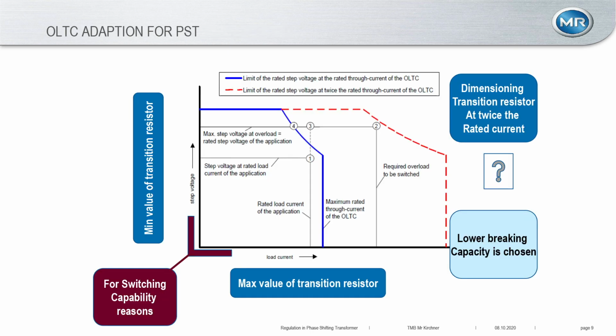If you look at point 1, that might be our working point for the onload tap changer. So that would be with nominal current. And now you would think everything is fine. And usually the standard would tell you that the switching capacity of your onload tap changer must fulfill the need that you can increase the load current to twice the nominal current, and then you're still within the red dotted line. So that would be the limit our OLTC is able to handle. Now you have to know with a phase shifting transformer, if you increase the load, the step voltage would increase as well. And in some cases, you have a working point where you would leave that red line. So if we double the load current from point 1, you would leave the red line to the right. So you would leave the switching capacity limit of our OLTC.